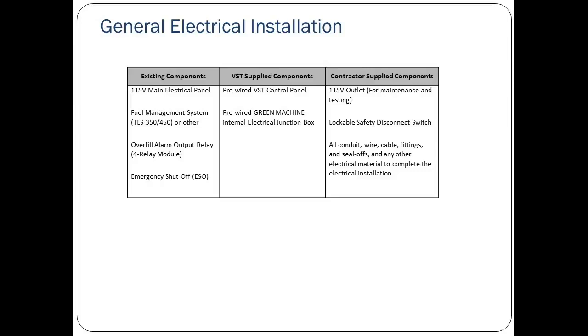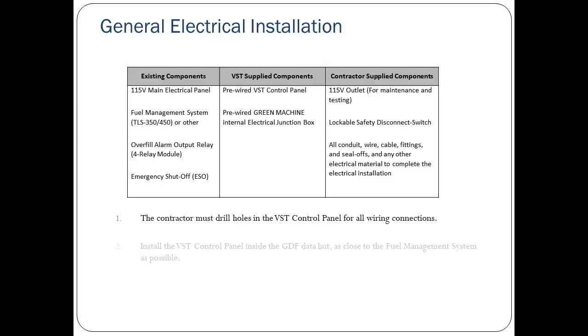The VST control panel does not have punch holes in the bottom, and these holes must be drilled for wire installation. The VST control panel is to be installed inside the GDF data hut. The closer the control panel is to the fuel management system, the better.